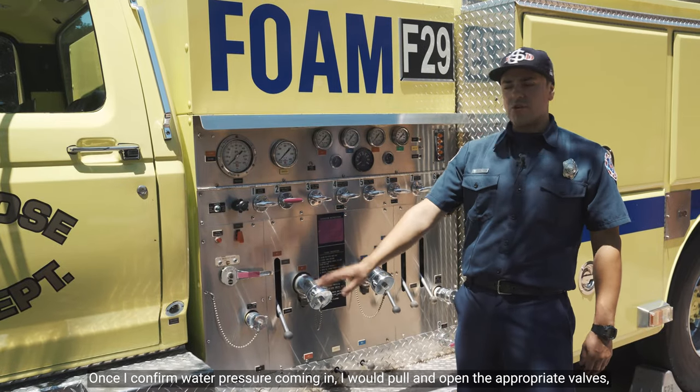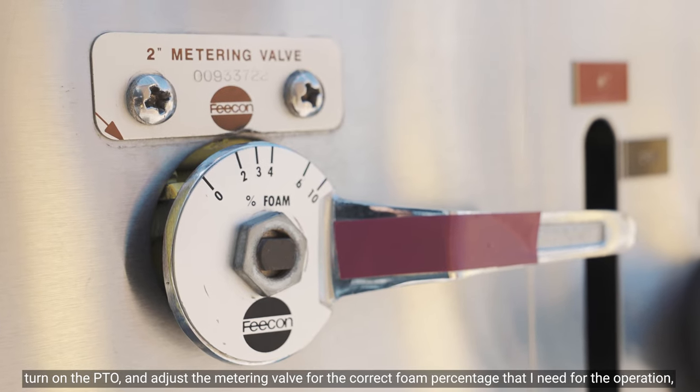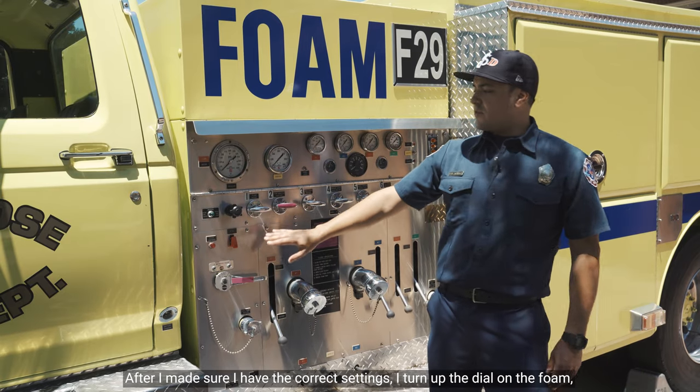Once I confirm water pressure coming in, I would pull and open the appropriate valves, turn on the PTO, and adjust the metering valve for the correct foam percentage that I need for the operation, whether I need 3% or 6%.